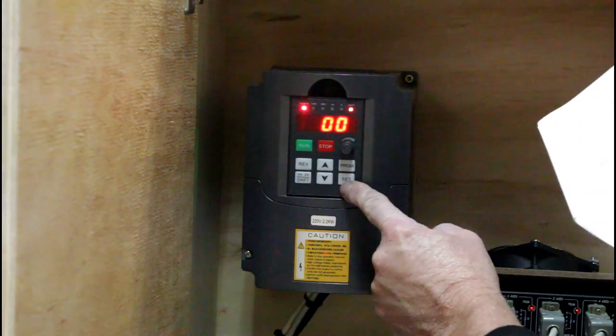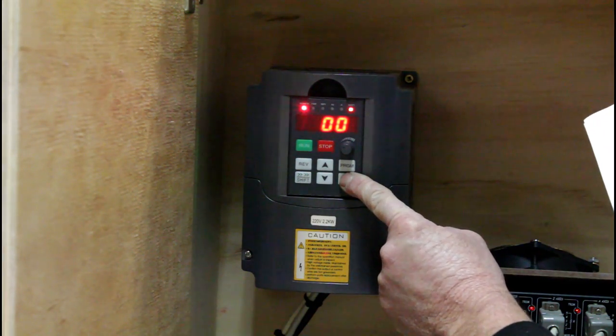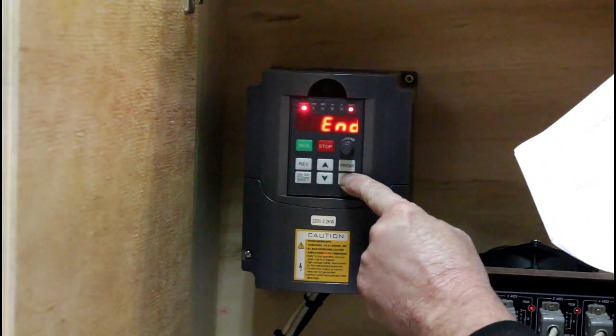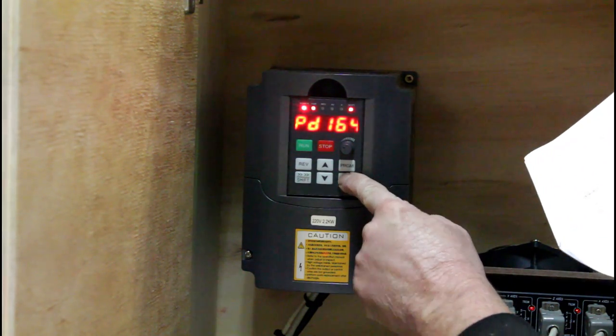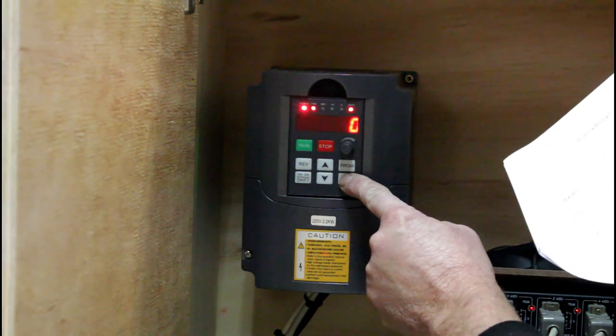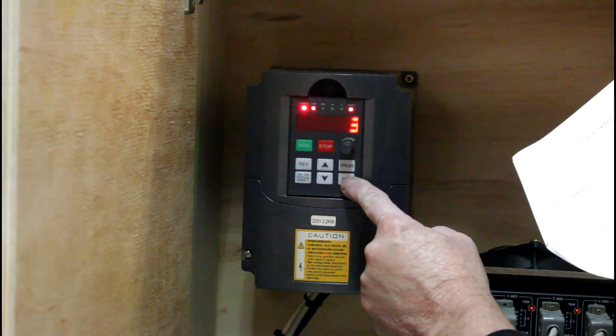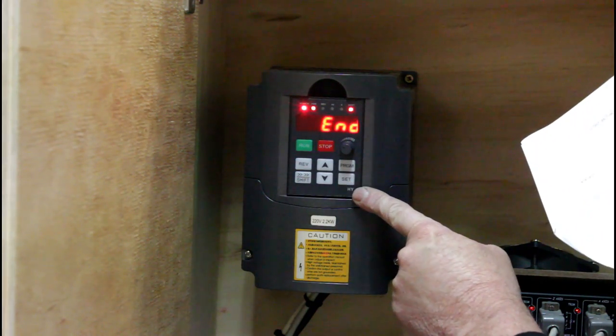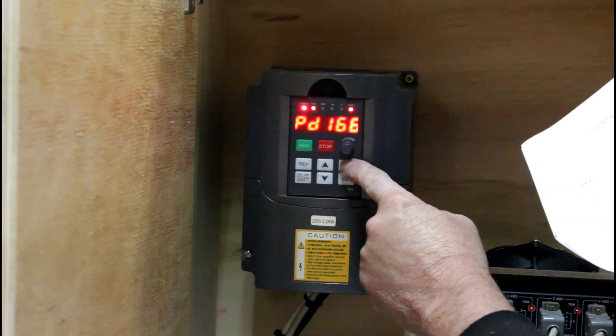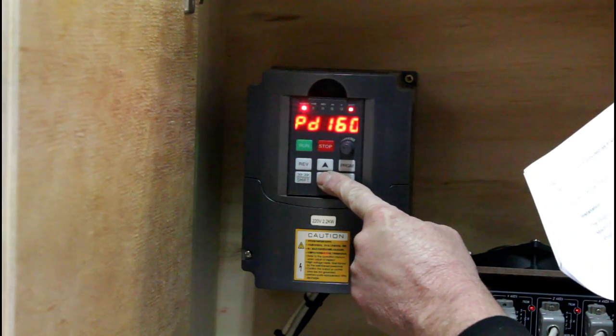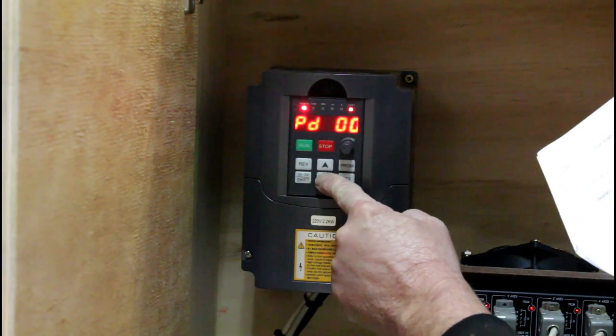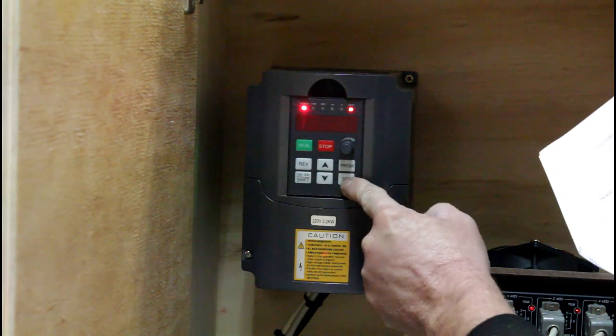Then register 164 we're going to change to a 1 and 165 we're going to set to a 3. Don't worry about it, all this information is in the document that accompanies the plugin. Once I've finished I go back and re-lock the VFD by changing register 0 back to a 1. This prevents accidental changes.